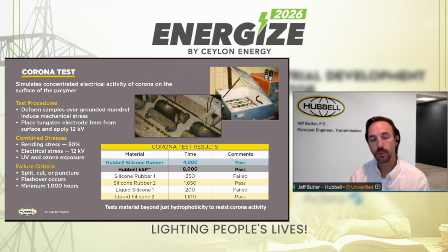But in this particular test, where you're breaking down the hydrophobicity and there is no moisture present where the silicone rubber could demonstrate the characteristics of hydrophobicity, you can see here in the table that the ESP material, the ethyl-based rubber, the ethyl and silicone rubber alloy, actually performs superior to the silicone rubber. This speaks to the durability of the ESP material to withstand electrical activity if it is present on its surface. In this test, we take a piece of rubber and bend it over a grounded mandrel, just a steel metal piece. As I mentioned, we put an electrode near the surface at 12 kV, and then we energize it for a minimum of 1,000 hours, and you can see the range.